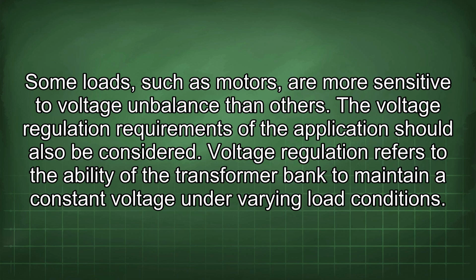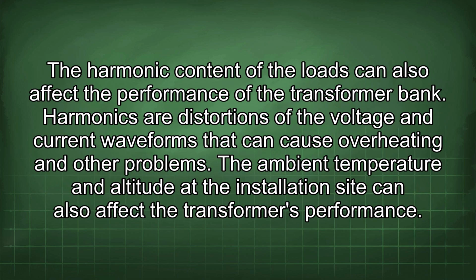The voltage regulation requirements of the application should also be considered. Voltage regulation refers to the ability of the transformer bank to maintain a constant voltage under varying load conditions. The harmonic content of the loads can also affect the performance of the transformer bank. Harmonics are distortions of the voltage and current waveforms that can cause overheating and other problems.